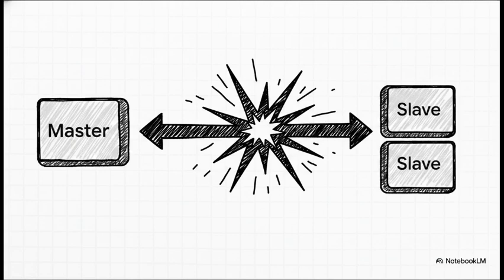To quickly recap the rest, remember that Modbus is a strict master-slave system. Always ensure your baud rate and format match the PLC exactly. Oh, and definitely make sure you have termination resistors installed at both physical ends of your RS-485 bus. That prevents nasty signal reflections. And finally, use that MBD diagnostic menu to spot any interference via those CRC errors.